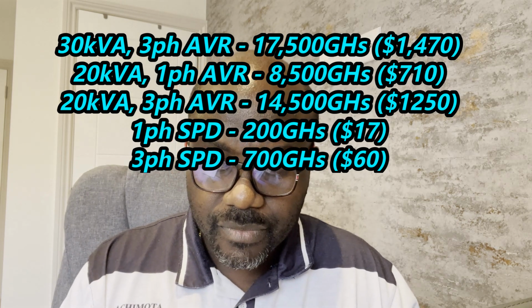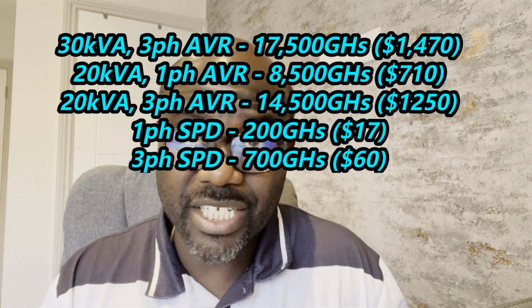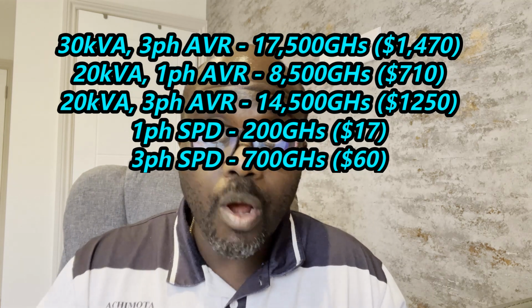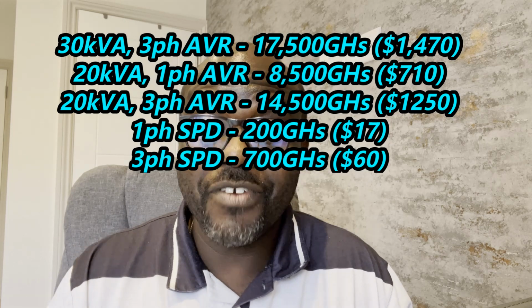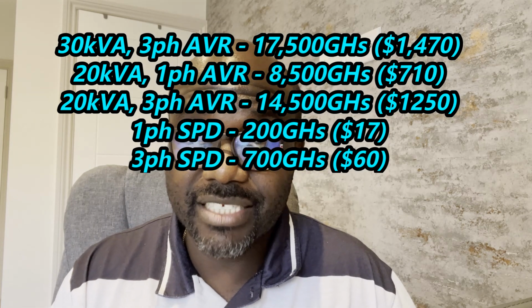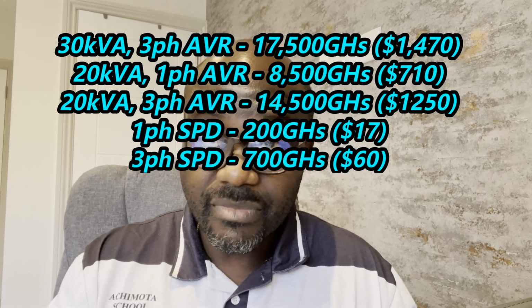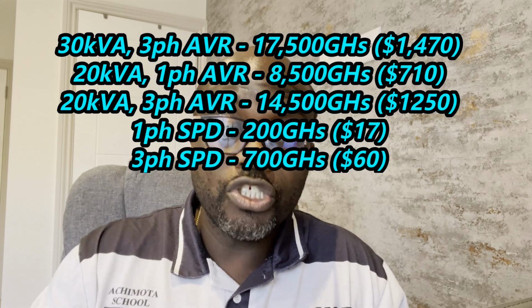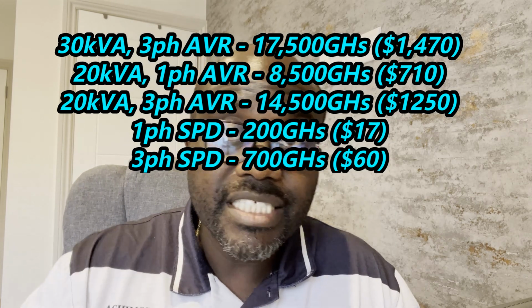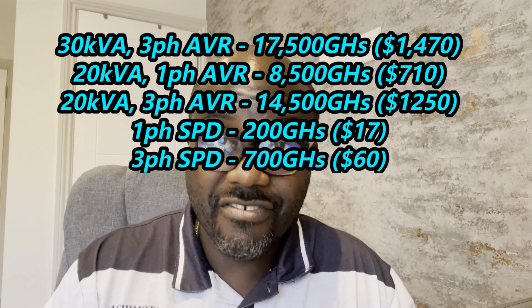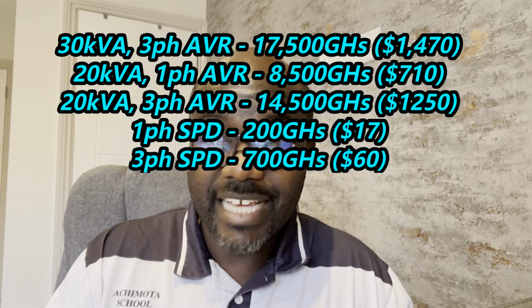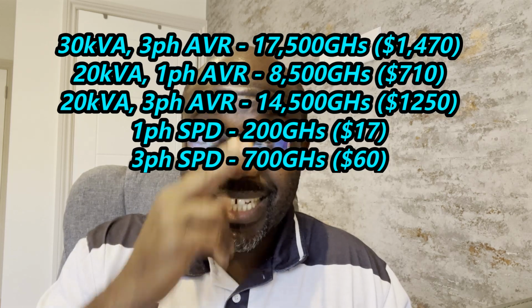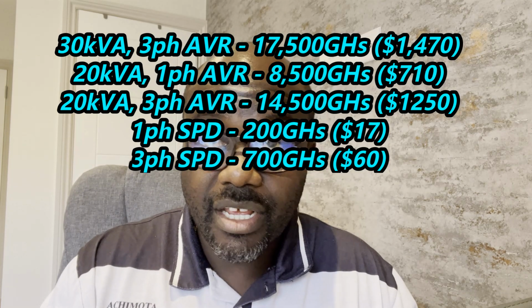In terms of the SPDs, they're much cheaper so they won't break the bank, but they'll save you in the long run from indirect lightning strikes. A single-phase SPD is about 200 to 300 Ghana cedis, and a three-phase SPD is between 600 and 700 Ghana cedis.